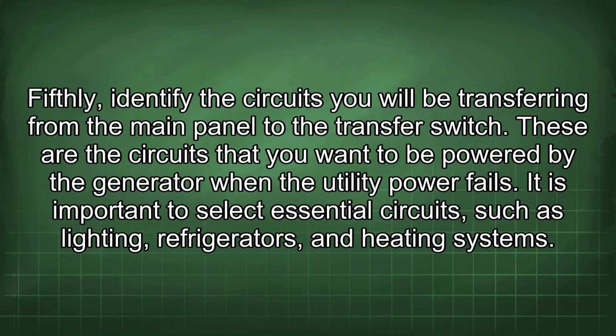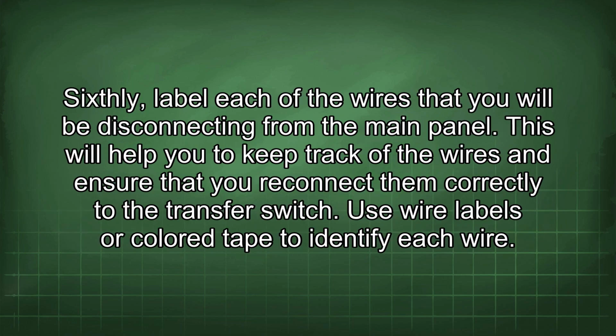Fifthly, identify the circuits you will be transferring from the main panel to the transfer switch. These are the circuits that you want to be powered by the generator when the utility power fails. It is important to select essential circuits such as lighting, refrigerators, and heating systems. Sixthly, label each of the wires that you will be disconnecting from the main panel.